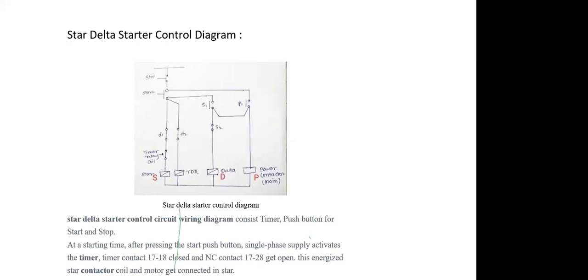So when we give the start command to the motor, these two contactors, star and P, are picked up. The motor starts, and this is the time delay timer. What is written here, TDR, is a time delay timer, and what time delay you set for this timer depends on the experience of the electrician or engineer who is associated.